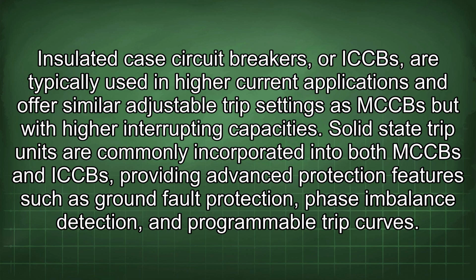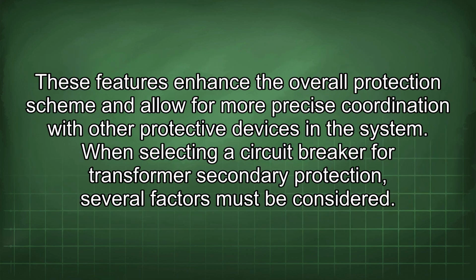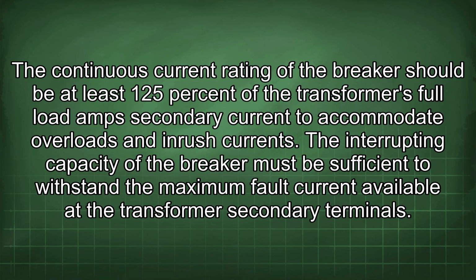Solid-state trip units are commonly incorporated into both MCCBs and ICCBs, providing advanced protection features such as ground fault protection, phase imbalance detection, and programmable trip curves. These features enhance the overall protection scheme and allow for more precise coordination with other protective devices in the system. When selecting a circuit breaker for transformer secondary protection, several factors must be considered. The continuous current rating of the breaker should be at least 125% of the transformer's full load amp secondary current to accommodate overloads and inrush currents.